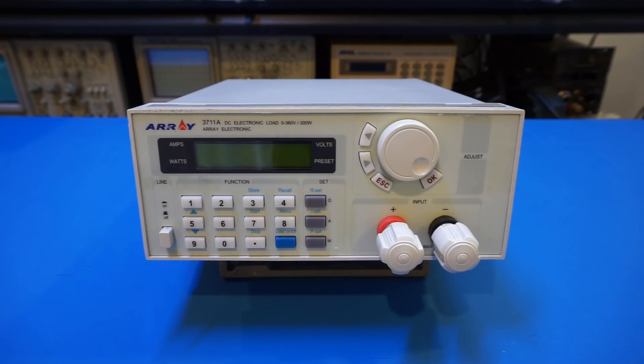Now this particular model is capable of handling loads up to 300 watts with a maximum current of 30 amps and a maximum voltage of 360 volts. There is also a 3710A version and the difference is the maximum load which comes in at 150 watts, and I would assume that the internal circuitry is largely the same as the 300 watt 3711A and the main difference would be the number of power MOSFETs and the control firmware.